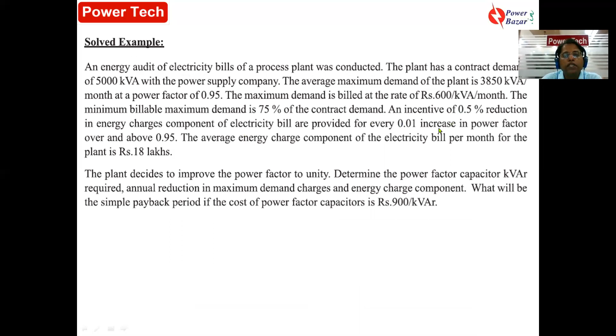Now power factor becomes 1, earlier the power factor was 0.95. So what is the reduction in energy charge? It is 0.5% for every 0.01 increase in power factor. Now, what is the increase here? 0.05. It is written here that there is a 0.5% reduction in energy charge component for every 0.01 increase in power factor. So how much incentive will he get? 0.05 into 0.5, it becomes 2.5% incentive you will get.